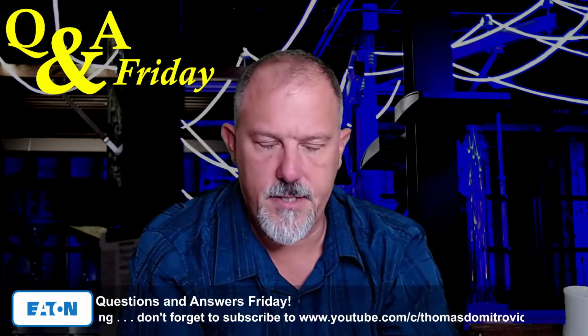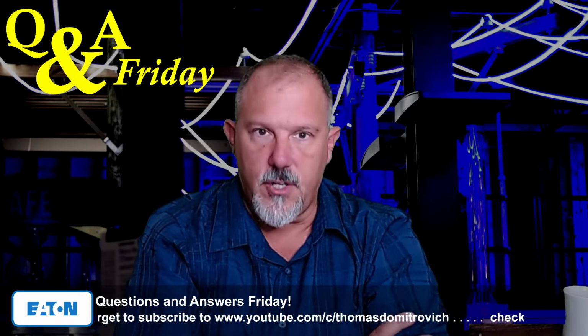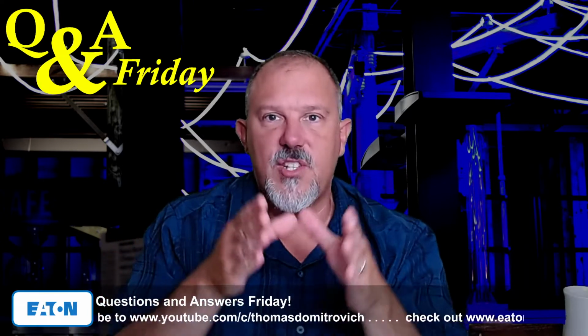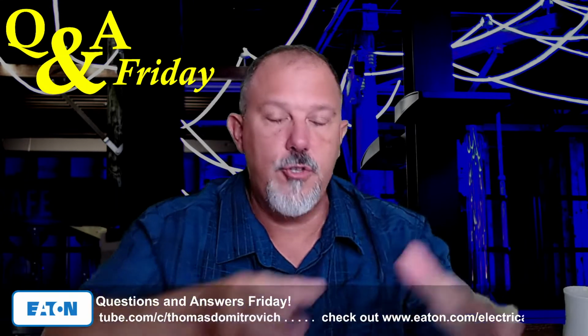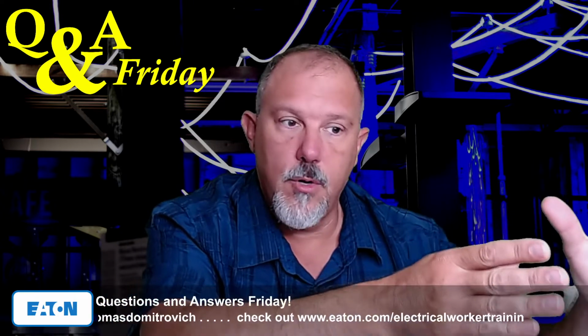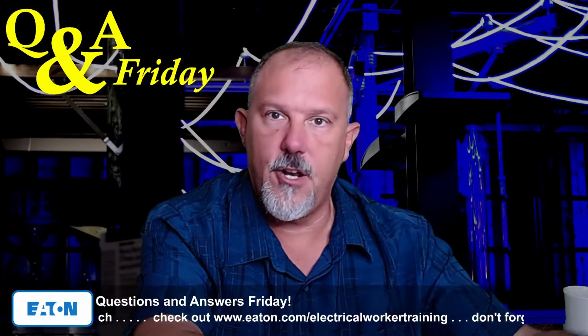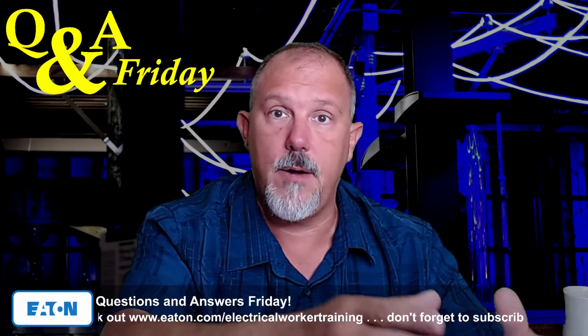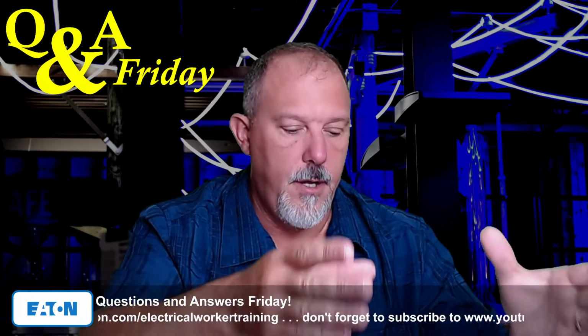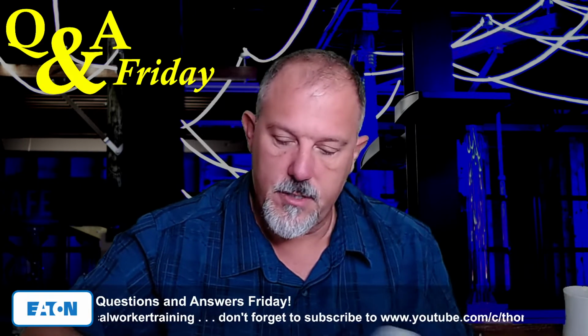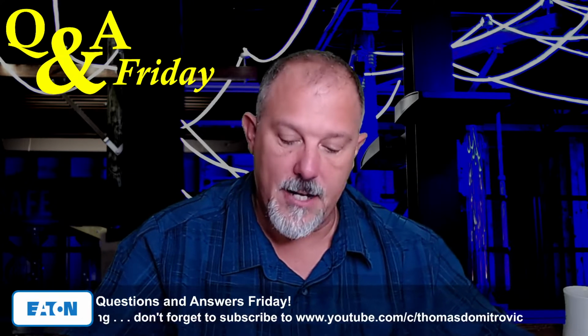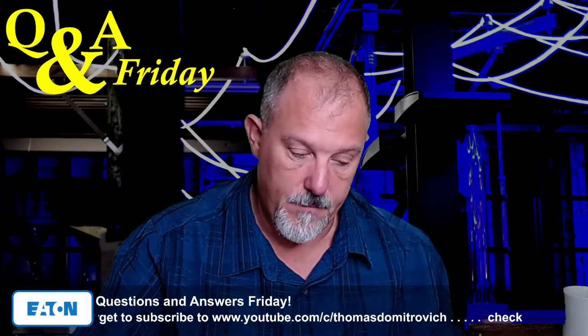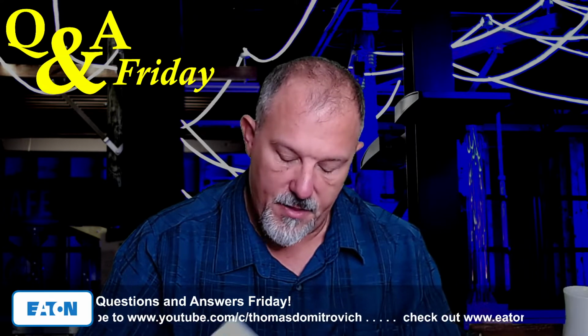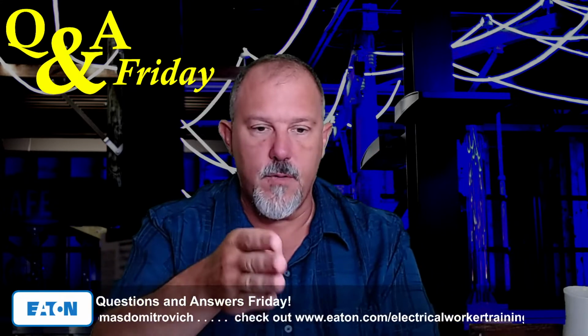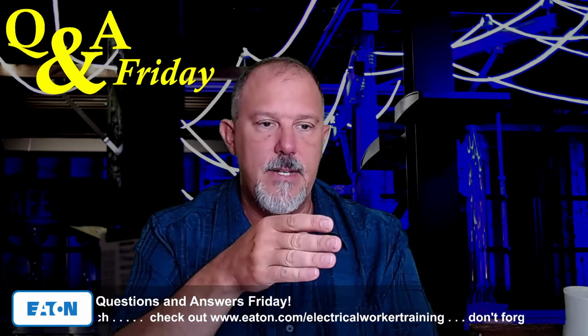Well, let's think about this. When you think about a 100% rated circuit breaker, what are we doing? How do we get there? The first thing that decides you're into a 100% rated system is when you do your load calculation. You take your non-continuous loads at 100%, and your continuous loads, 3 hours or more, you add in at 100% and you don't do 1.25. And then you're going to come up with a number for an ampacity, and you're going to protect it at that size.